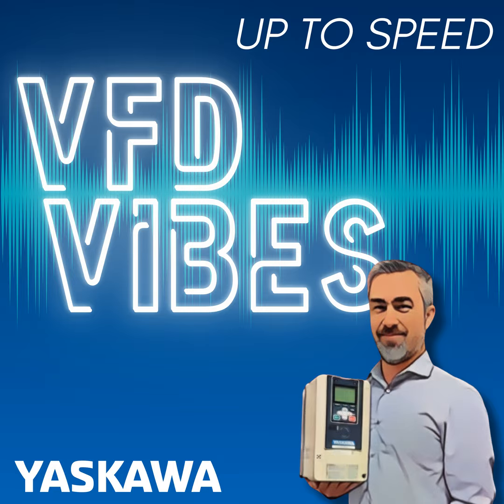Now, the term grounding, we even talk about equipment grounding. Grounding and bonding are used synonymously, really, in real life. Like we talk about running a green wire from the cabinet to the grounding bus that's on the back panel and this type of thing. Well, we call it grounding when the code will refer to this as bonding. So bonding is really just tying different devices or pieces of metal, for that matter, to the ground. Exactly. It's just when you talk about grounding, it's maybe a device that is specific to having a ground or needing one, whereas bonding is taking something like a panel door, which we don't want power running through when we touch it.